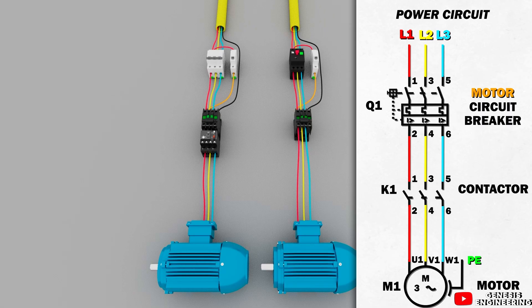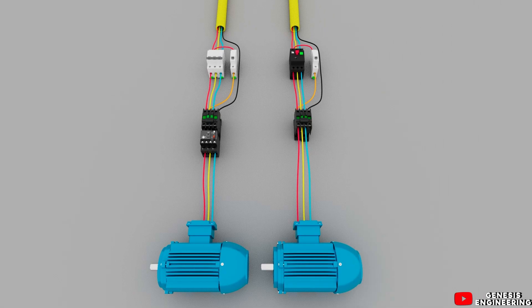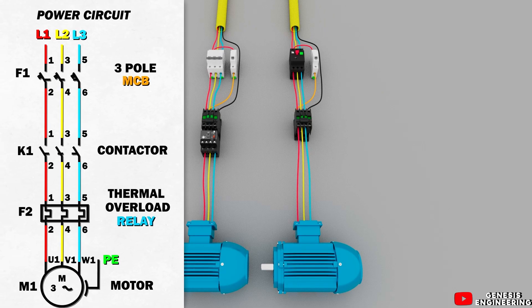When the circuit is on, the motor circuit breaker contacts are closed. But if there is an overload in the motor, the motor circuit breaker will identify the overload and will open the power contacts to turn off the motor. With the thermal relay it is different, because the power contacts of the thermal relay do not open like the motor circuit breaker does.